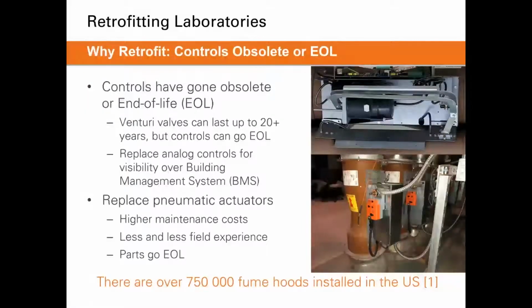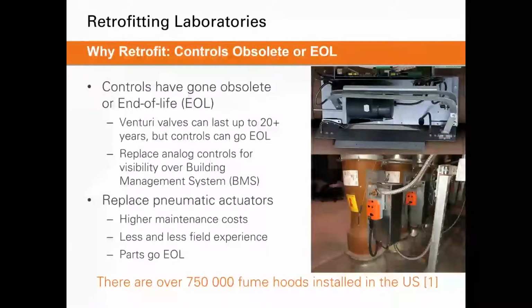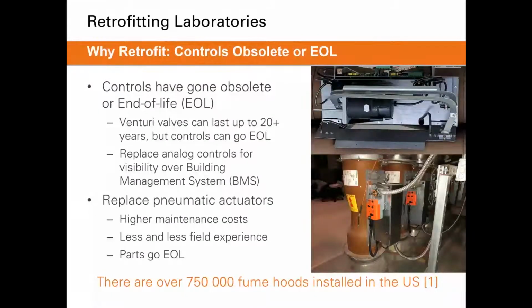A couple of reasons why you would want to consider or may have to do a lab update would be, the first one would be if your controls have gone obsolete or end of life. Venturi valve technology is known to last up to 20 plus years in the field. It's been market proven. Venturi valves are essentially maintenance free and they're very robust mechanical designs. So if they've been properly selected and if the coating has been properly selected, then they will last that long in the field, over 20 years. In that time, though, there's a very good chance that the controls serving that valve are going to go end of life.